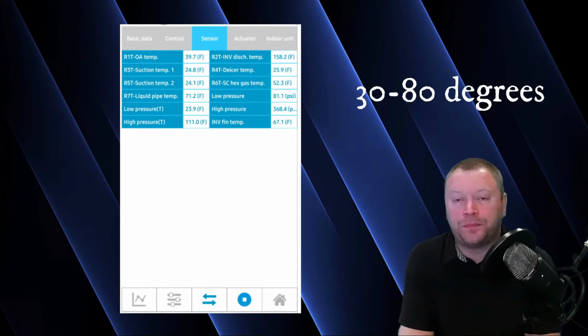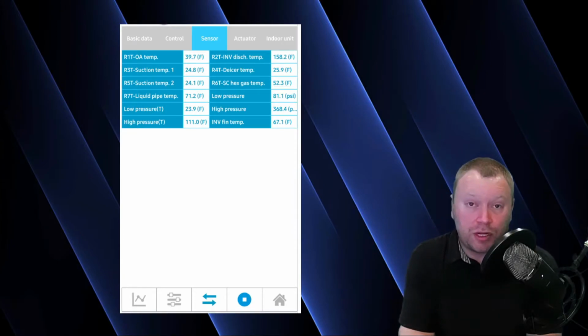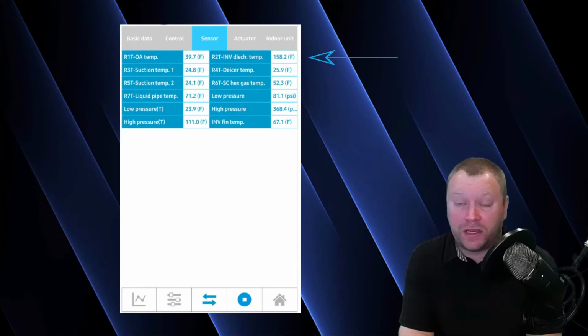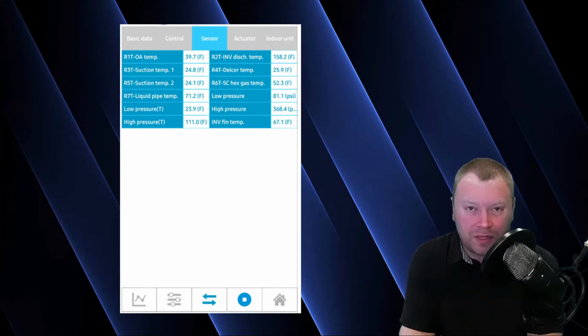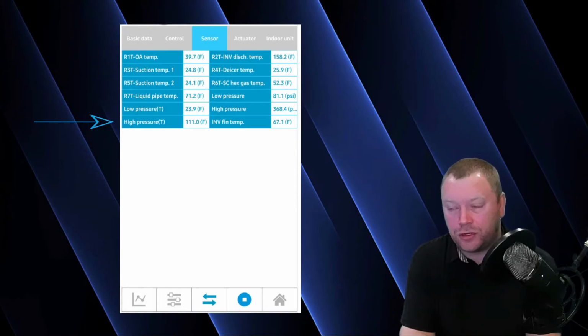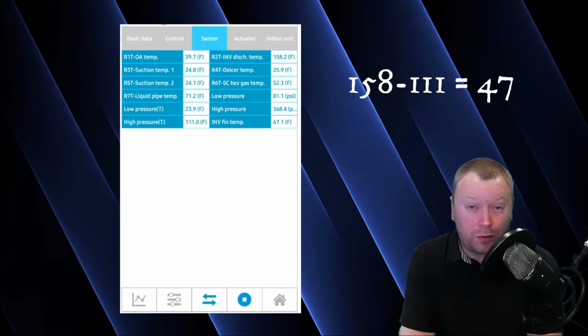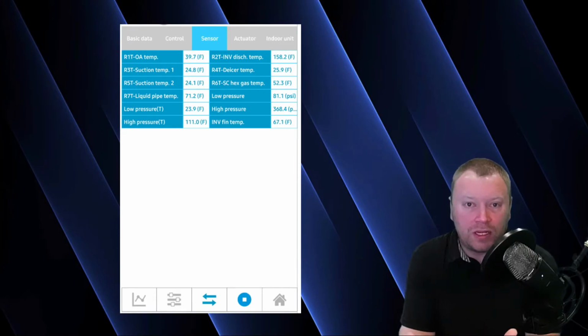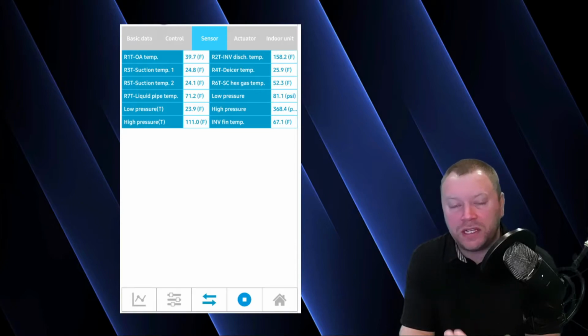In this particular case at my house, my discharge temperature was 158 degrees. My condensing temperature, indicated by the line item that says high pressure T temperature, was 111 degrees. And so my discharge superheat was approximately 47 degrees. So I was, not exactly in the middle, but I was in between 30 and 80, which is good. The next thing that I do is I follow the refrigerant flow depending on what mode I'm in. And so we discussed this in the mini split video as well, but where is the refrigerant going when I'm in the heat mode after it leaves the compressor?